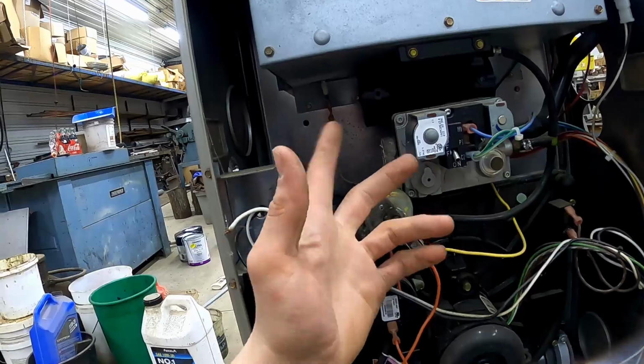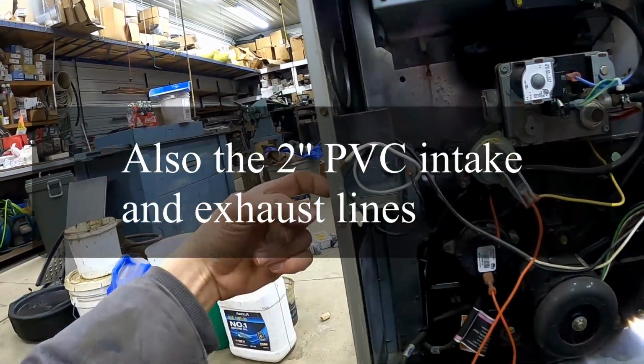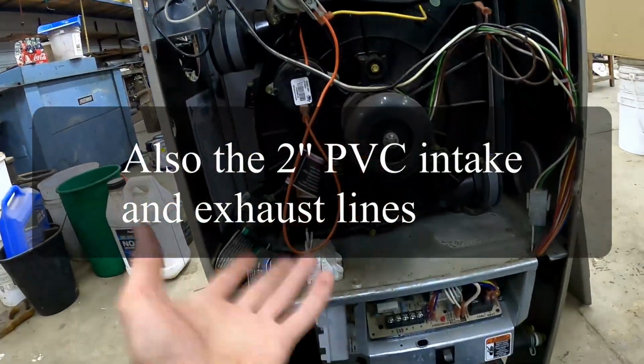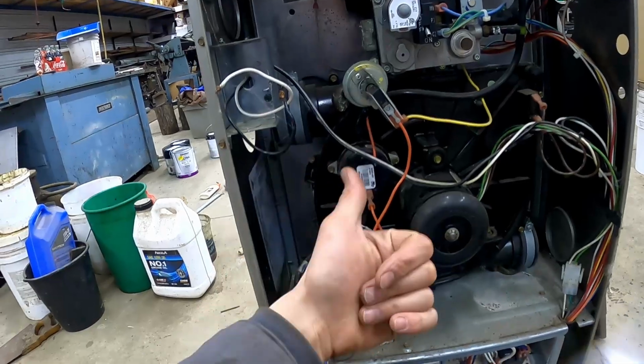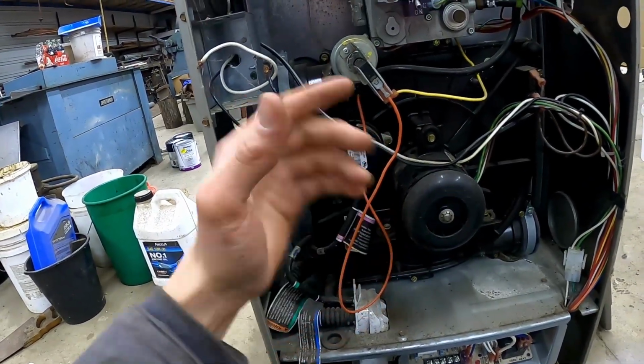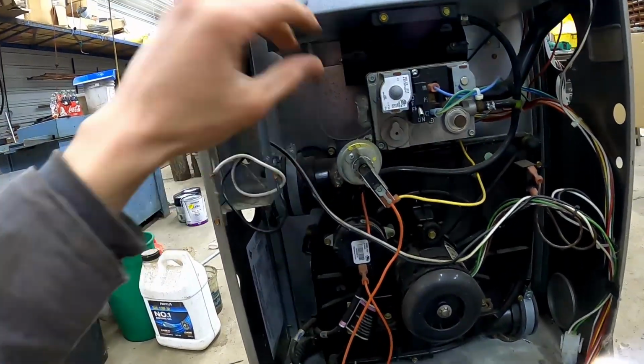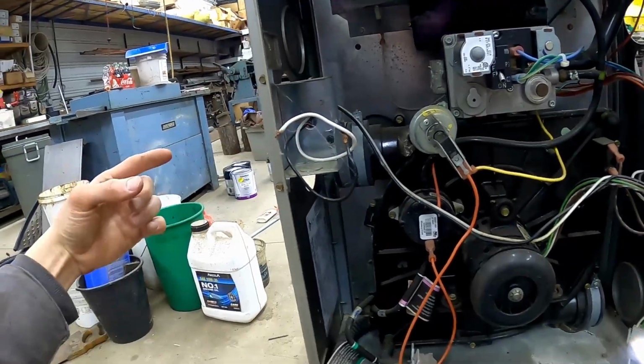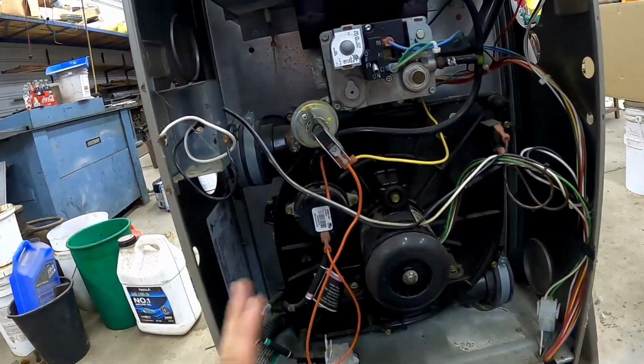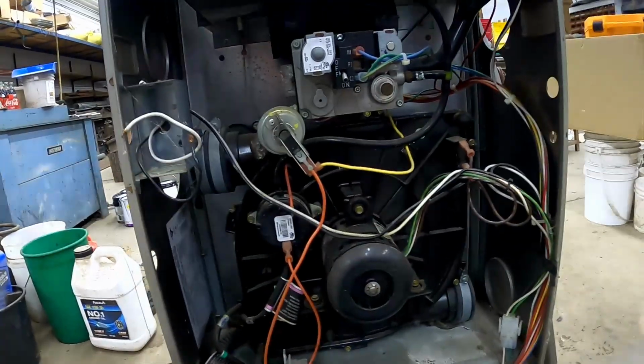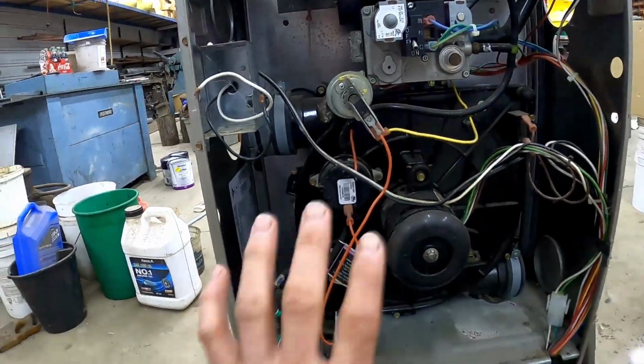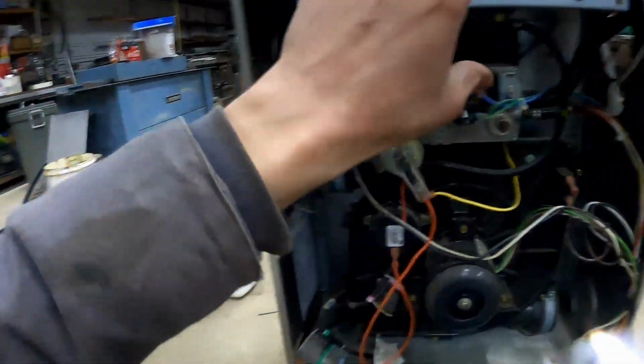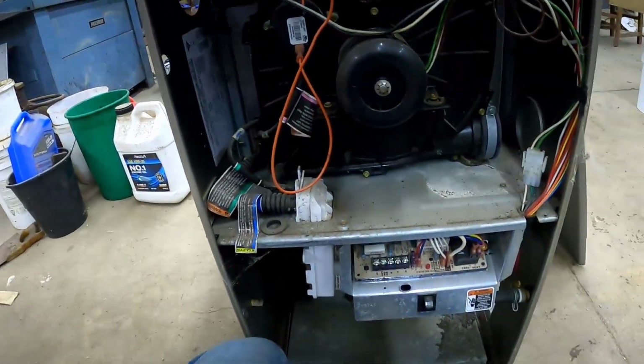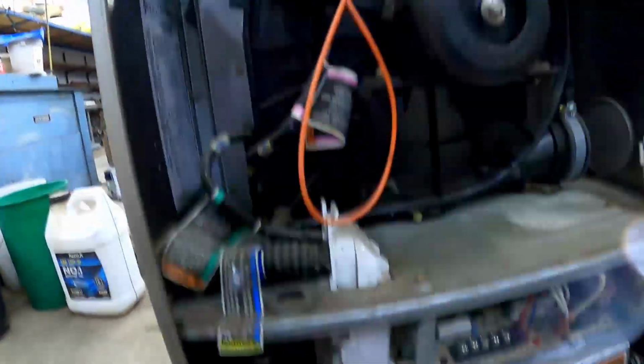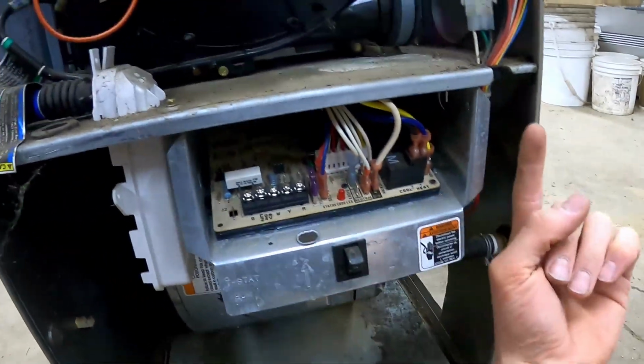The gas line is already disconnected on this unit, and the electrical coming in on the side is already disconnected on this unit since it's currently not installed. But you'd want to shut the power off, shut the gas off, and disconnect the gas line and the electrical coming into the side here so that you can move this stuff out of the way. And then basically we're going to take the combustion blower out, set that aside, the burner box out, set that aside, and then also remove a couple of screws that are going up from the blower into this front plate.